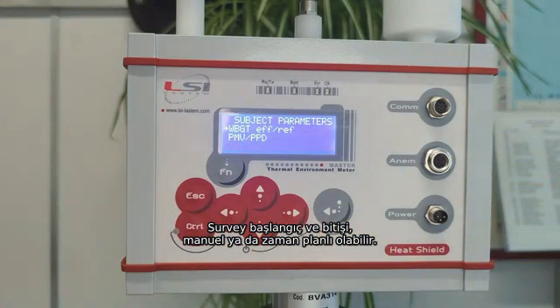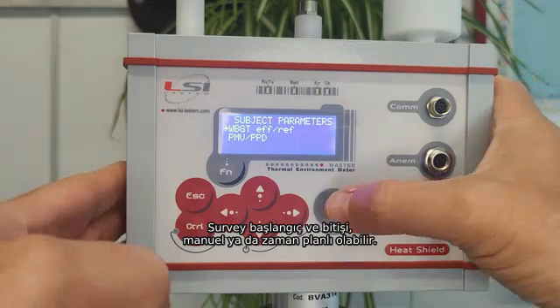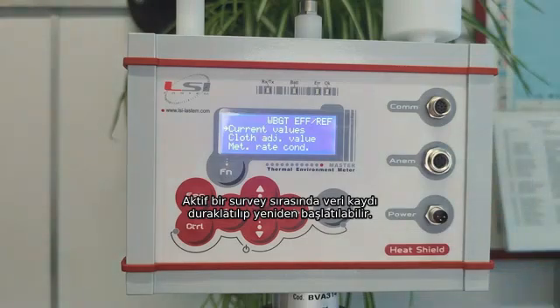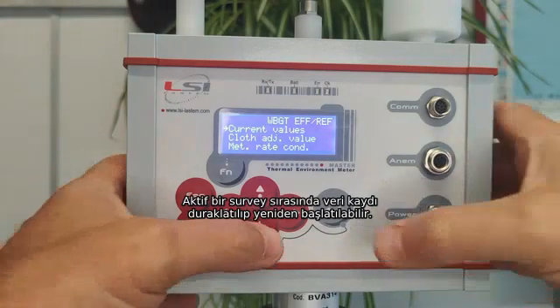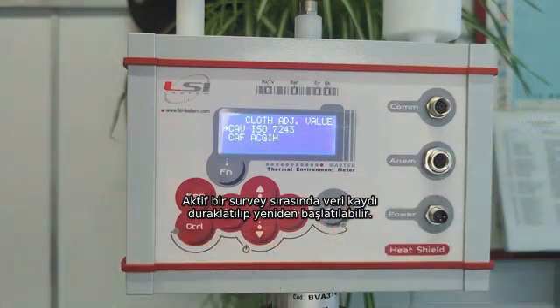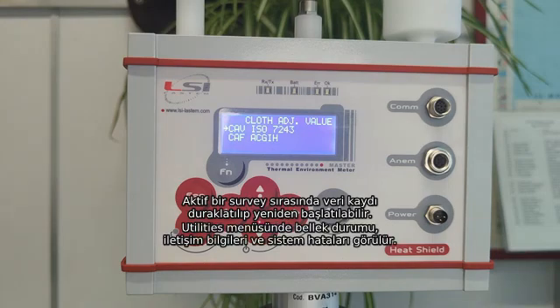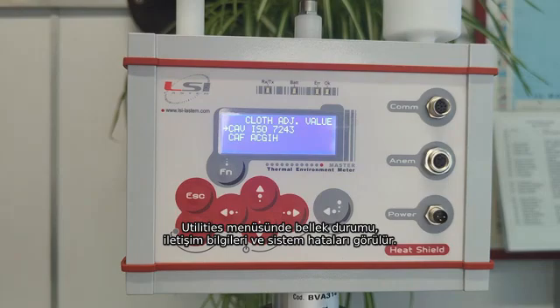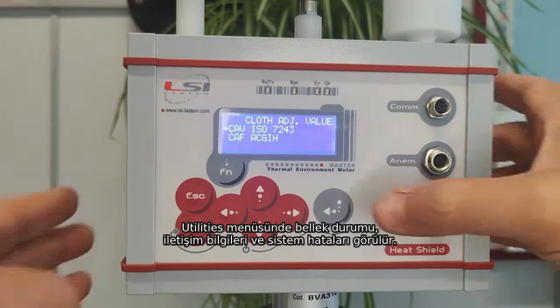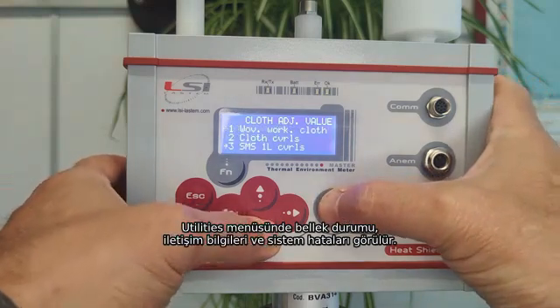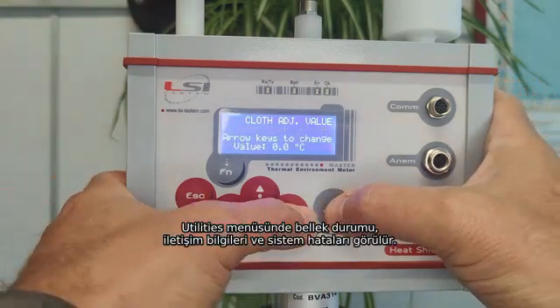Subject parameters are different if we decide to perform WBGT or PMV-PPD calculations. To obtain the correct WBGT effective value, it is required to enter the clothing adjustment value. Clothing descriptions and values are taken from the lists by ISO 7243 or by the American ACGIH. The value corresponding to each selection is proposed by HeatShield and it can be modified manually by the operator.